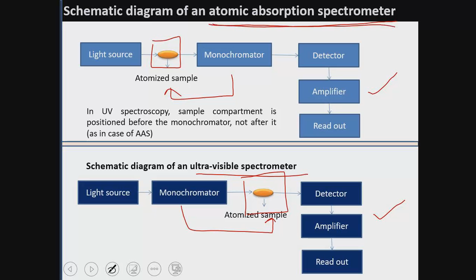This is the schematic diagram of atomic absorption spectrophotometer. There are four major parts. First is the light source, that is hollow cathode lamp. Second is the atomizer. Here in this scheme, the atomizer shown is flame atomizer, then the monochromator, and the fourth part is the detector. Here the light source used is hollow cathode lamp. Then the second part, atomizer. This atomizer may be of various types, but here the atomizer shown is flame atomizer.